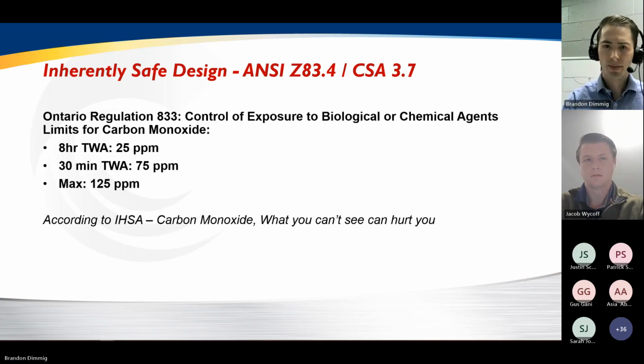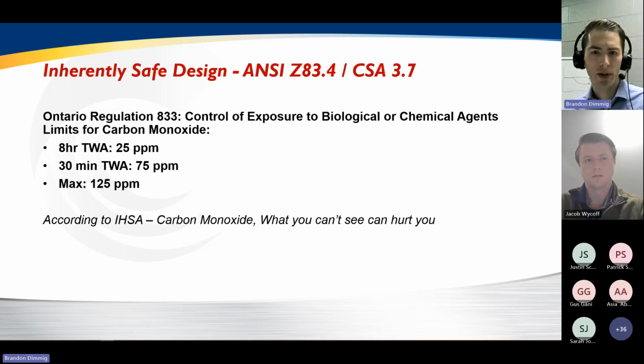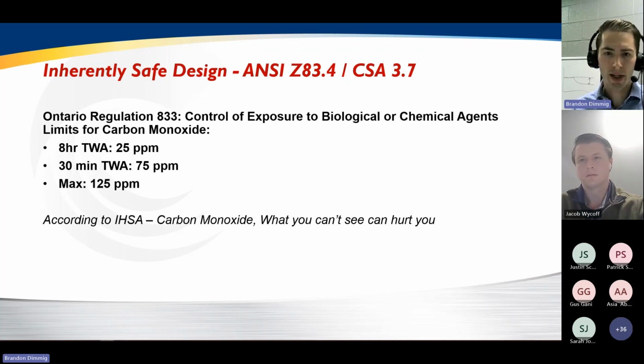of different cases. I know OSHA, which is what we use in the US, limits an 8-hour time-weighted average for carbon monoxide exposure to 50. Perhaps you all know more about this than me, but it looks like Ontario Regulation 833 in the IHSA, so compared to OSHA, your limitations are a little bit lower. You've got a 25 part per million time-weighted average carbon monoxide exposure. But again, you can see, even from a certification perspective, we're considerably lower than the exposure limits for carbon monoxide.